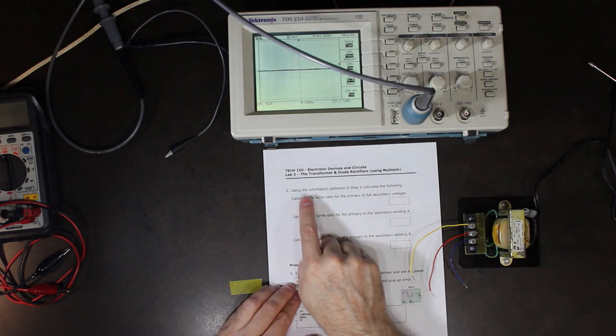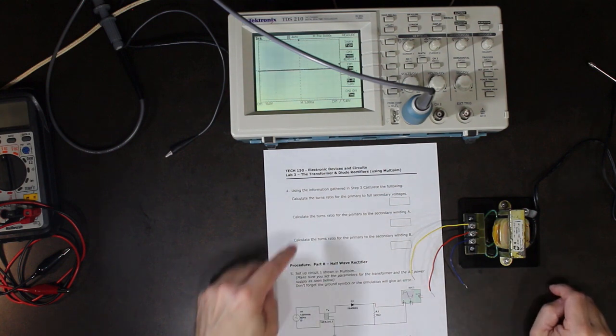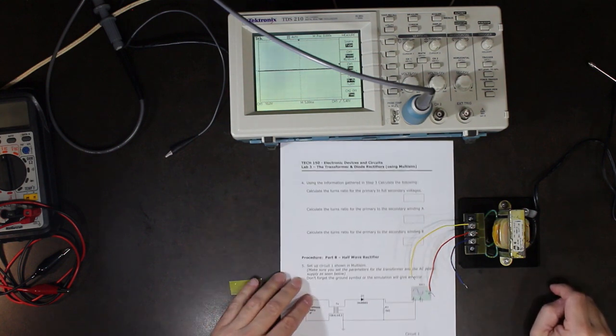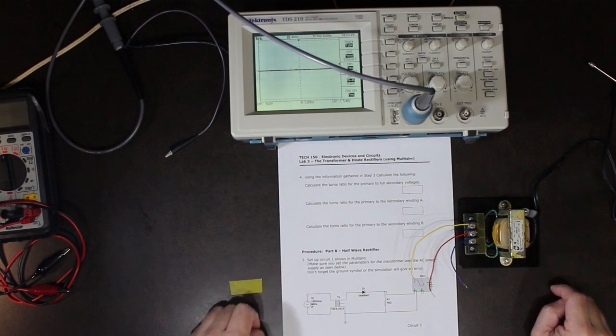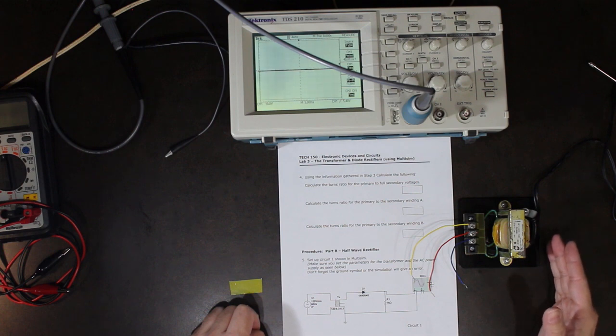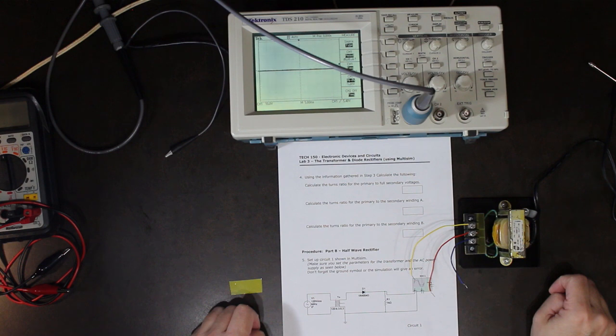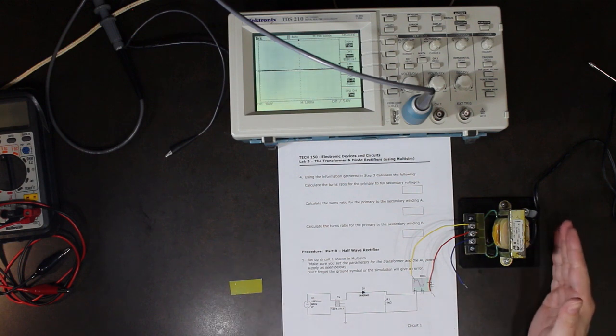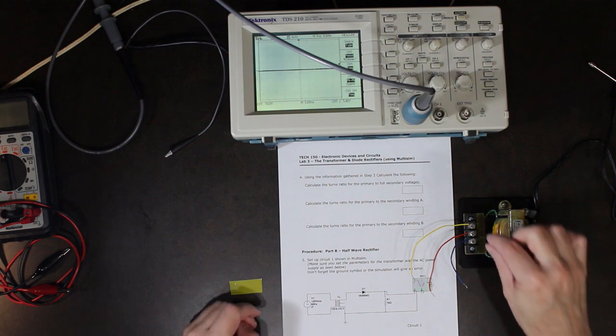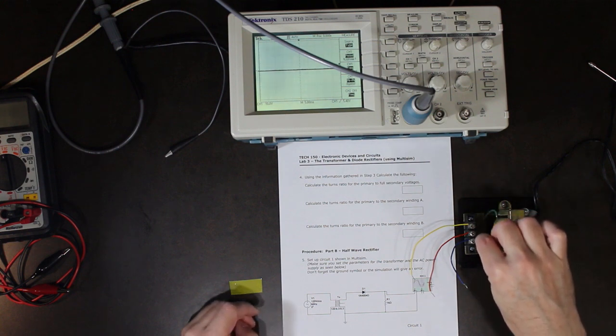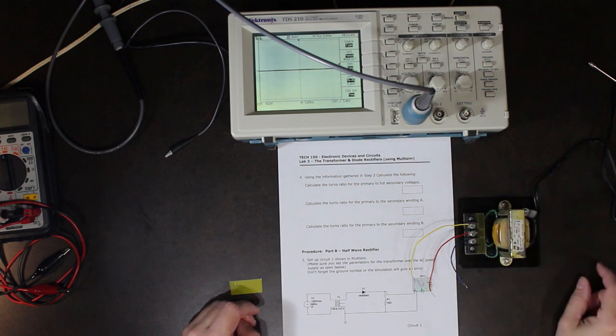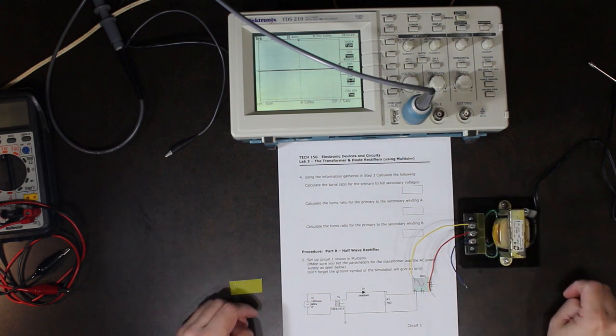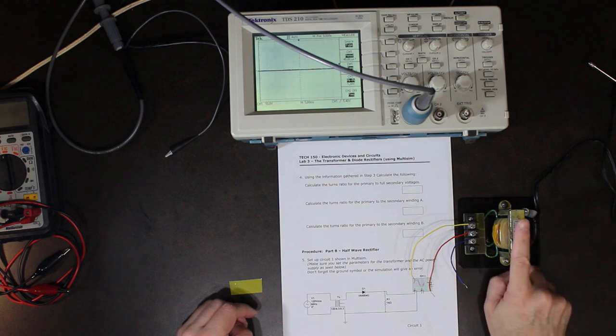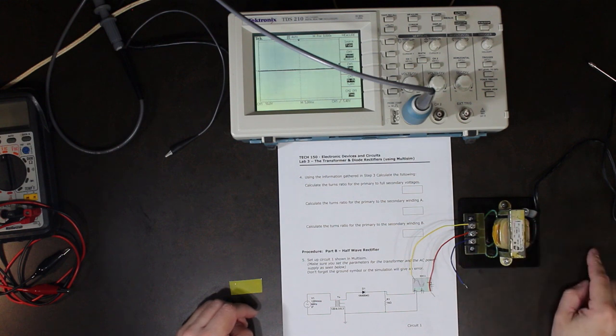Using the information gathered in step 3, calculate the following. You've got three calculations you can do based on the measurements we just took: the voltages coming into the primary and the voltages coming out of the secondary. You know what the voltage is coming in, and we know what the voltage coming out at A, out at B, and out at the total are. And you can figure out what the actual turns ratio is for this particular transformer.